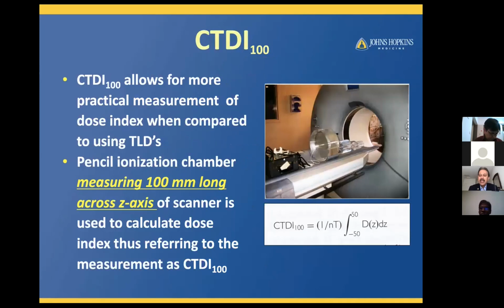In reality, what we do as physicists, many of you know, is use CTDI with the standard phantoms. Fortunately, these standard phantoms have been standard from the time CT was developed from 1974 onwards. The large one is called a body phantom, and we use a pencil chamber. A typical pencil chamber is about 100 millimeters in length, and that's why we call it CTDI 100, the computed tomography dose index 100, indicating the length of the chamber. It is given by this formula, integrating the dose on either side of the slice obtained in this phantom, which is 100 millimeters, or 10 centimeters, long.